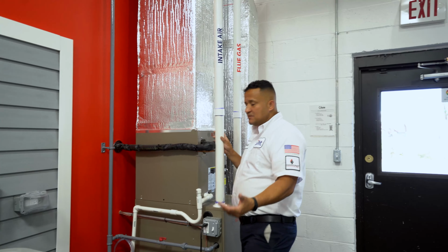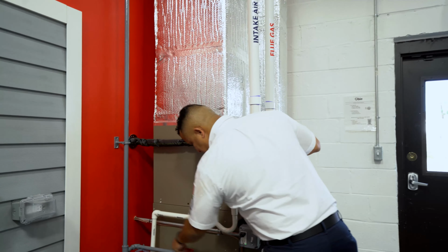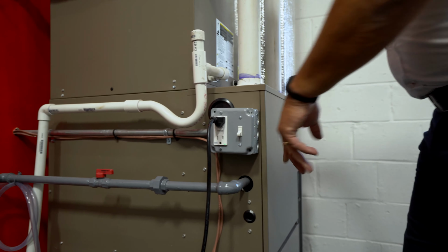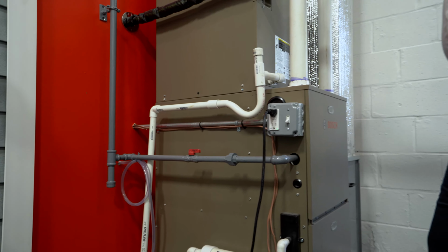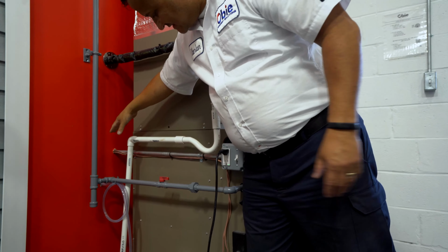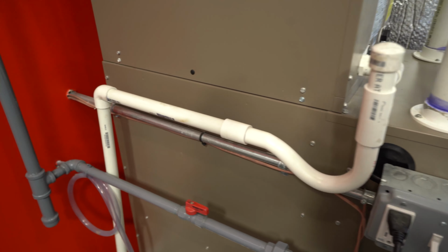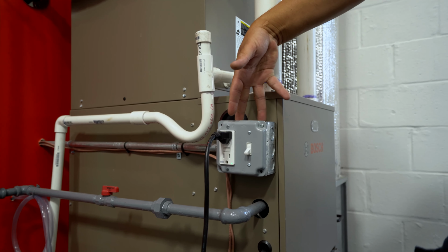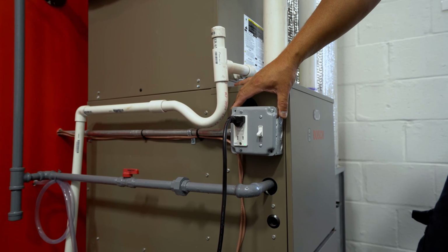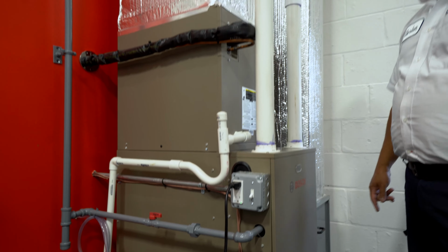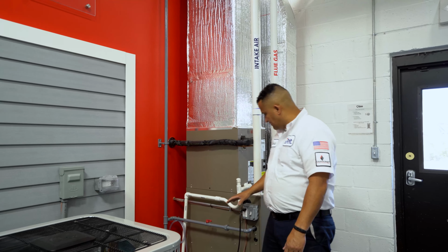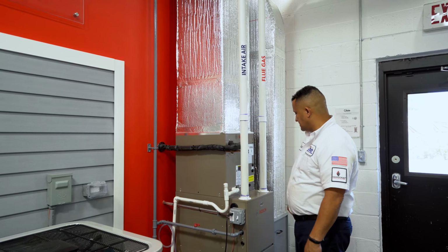It sounds like a lot, but here in Massachusetts, to do the gas, this is the gas line that goes inside of the furnace, you have to be a licensed plumber to connect this, to touch this and to connect it inside of the unit. This part here is the electrical, coming out from the wall and connecting here. To do those connections, you have to be a licensed electrician. Also, you need a gas permit for this and you need an electrical permit for this.